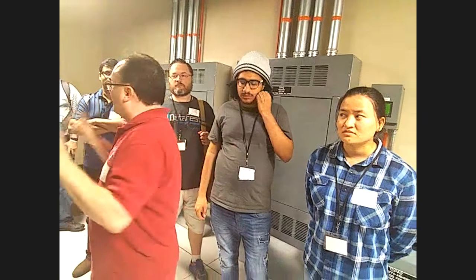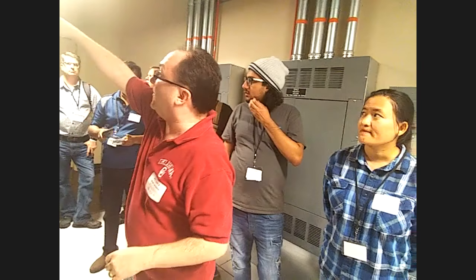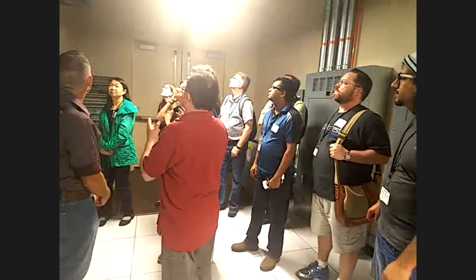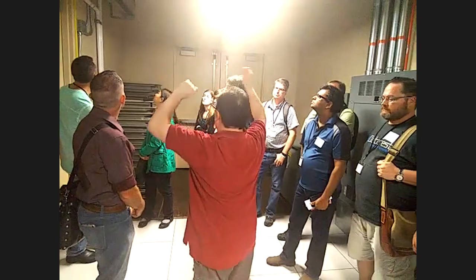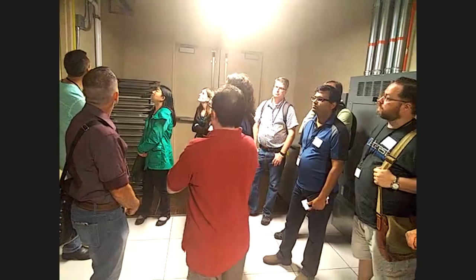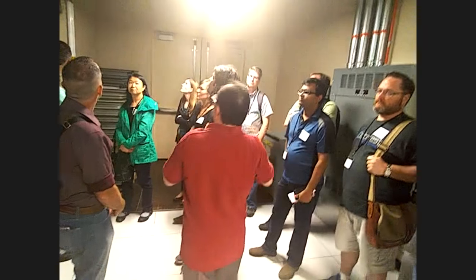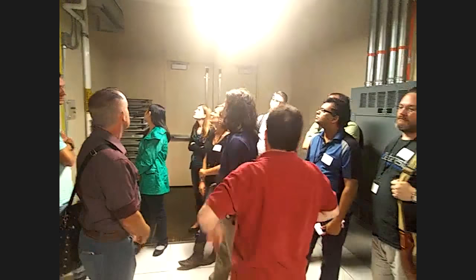So that's the cooling system. Now up there, it's not doing its thing right now, but like you go to a restaurant and it's a hot day and they have the outside area with the thing that shoots mist around. Why does it shoot mist around at the restaurant? To keep you cool. Why does it shoot mist around in the data center? The data center's already chilled, right? So why would we do this? Humidity control, exactly correct. What happens when humidity is too low?